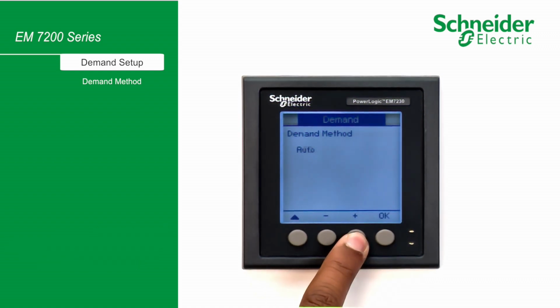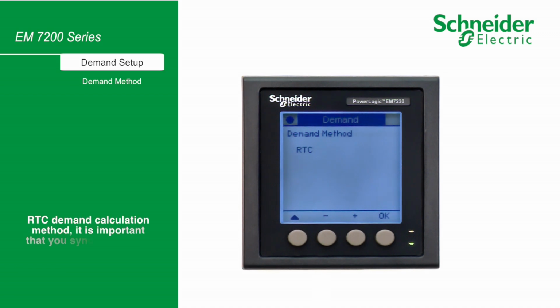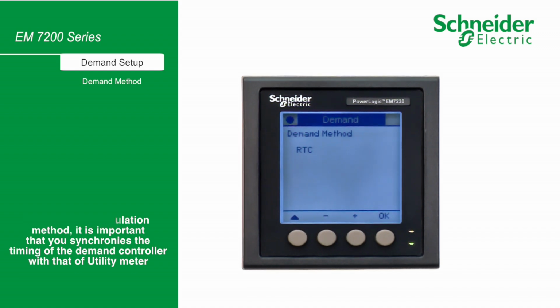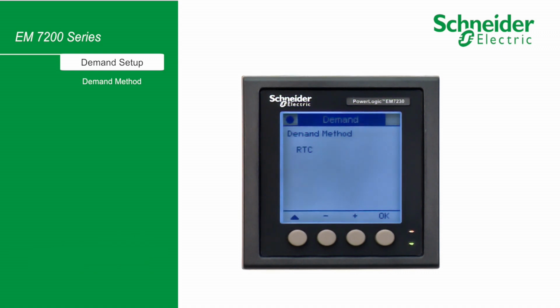It could be auto or sliding window type, or user type, or real-time clock, also called fixed window type. For the RTC demand calculation method, it is important that you synchronize the timing of the demand controller with that of the utility meter. Let's select RTC.